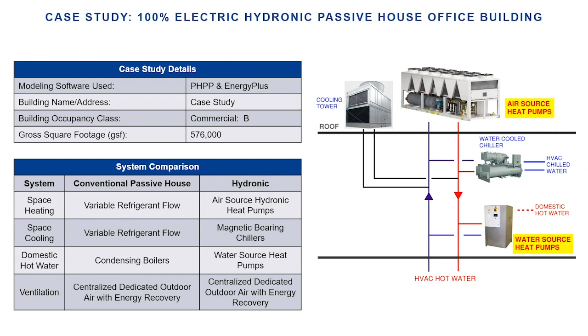So these are the results from this case study. The PHPP model is shown in blue here. The Energy Plus model is shown in green. The baseline case, as I'll call it, is the conventional passive house multifamily building, or the systems you might expect to see in that type of building, with the variable refrigerant flow for heating and cooling and the gas domestic hot water, as modeled in the Passive House Planning Package, PHPP. And then the Energy Plus model for this base case was within 1%.